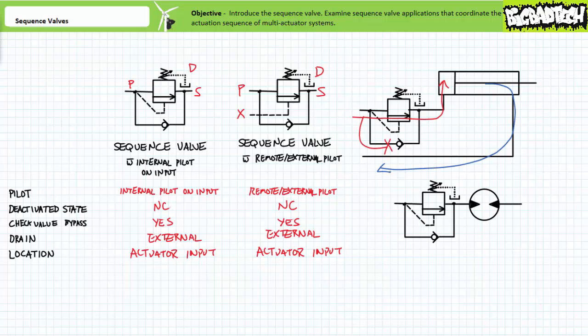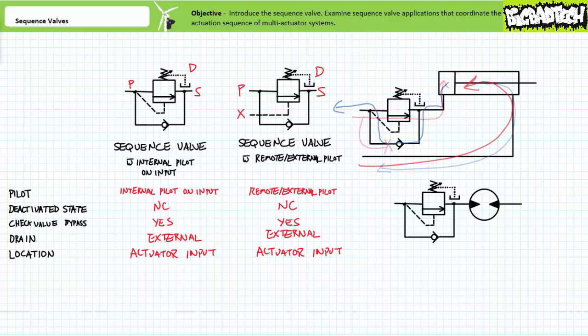Similar to guidance issued in the flow control methods lecture, it is not necessarily the valve or actuator port that determines the sequence valve's orientation, but rather the check valve bypass that does so. For example, this sequence valve is on the input of the cap end of this double acting cylinder. Only when pressure on the input port exceeds the set value does the sequence valve open and extend the cylinder. When flow switches direction, the sequence valve is bypassed through the check valve bypass, and the cylinder retracts with no pressure precondition.